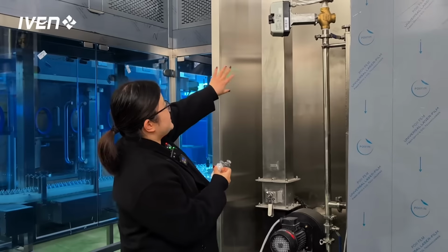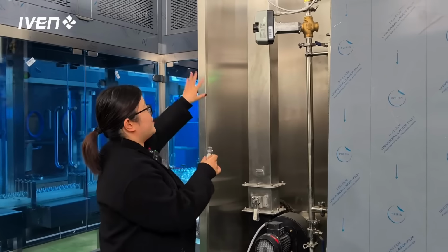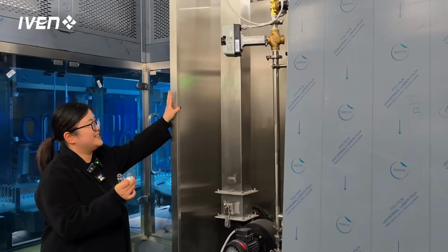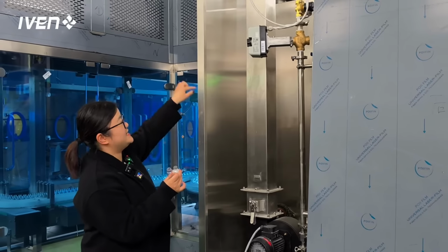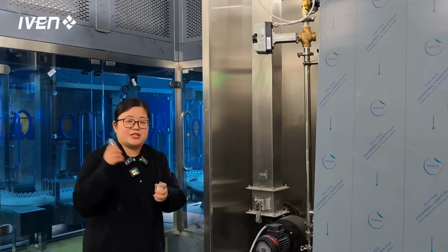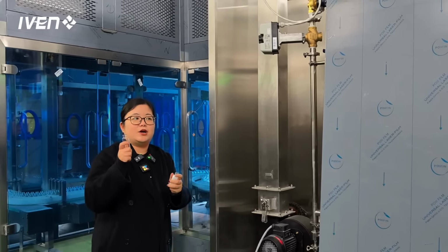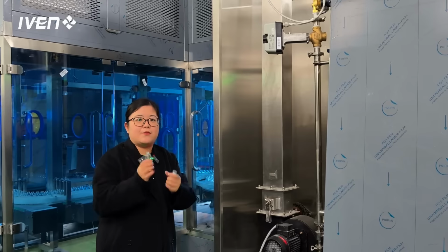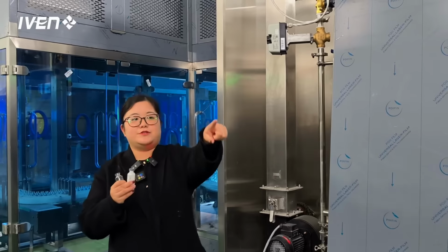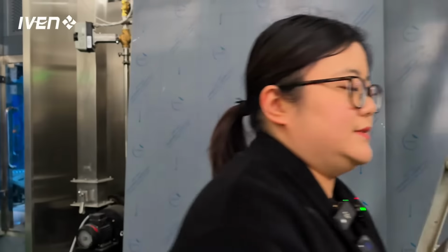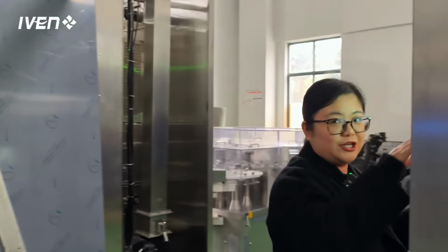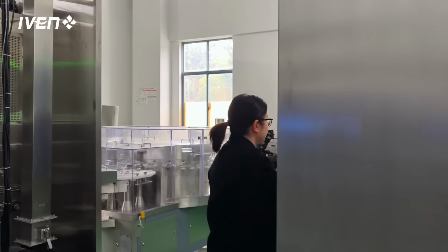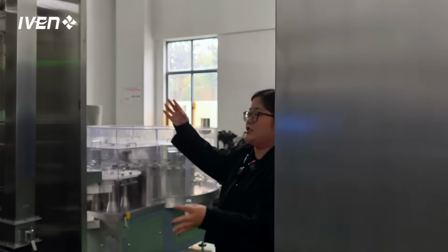At the end of this machine, we are equipped with a temperature probe. Now we can see the probe inside. Each batch's vial cooling time and heating time will be recorded to the HMI, and then the data can be downloaded. That's the sterilization tunnel.